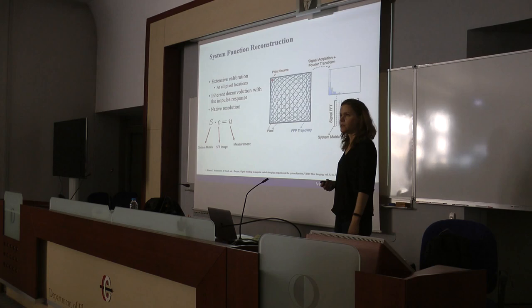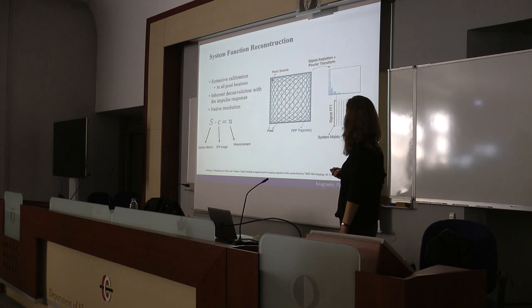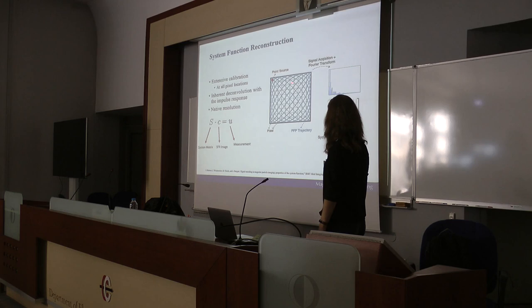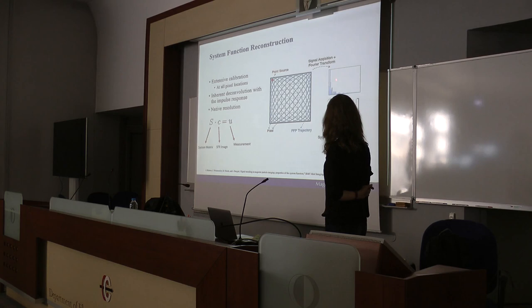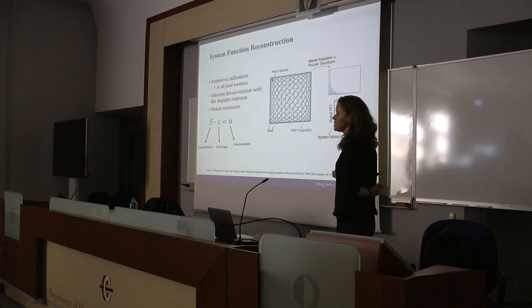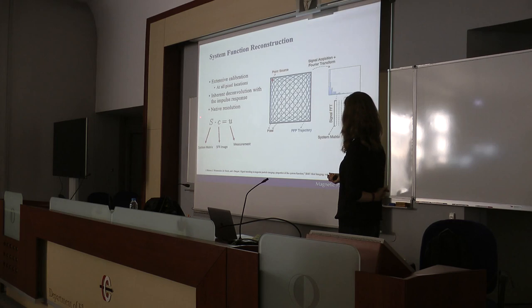There are currently two different image reconstruction schemes used in MPI. The first is system function reconstruction, where a 2D or 3D trajectory sweeps the field-free point in space. Calibration measurements are taken first: the imaging field of view is divided into a grid, a point source is positioned at each grid location, the trajectory is applied, the signal is recorded, its Fourier transform is taken, and it is placed into a system matrix. For a 40 by 40 grid, this process is repeated 1600 times at all positions to build the large system matrix S.